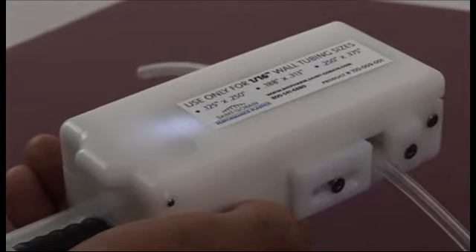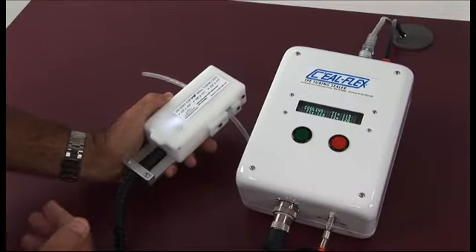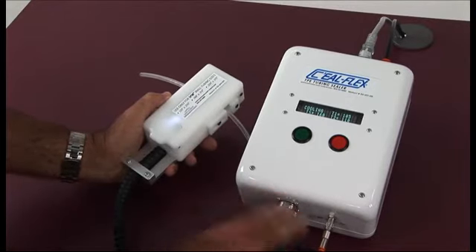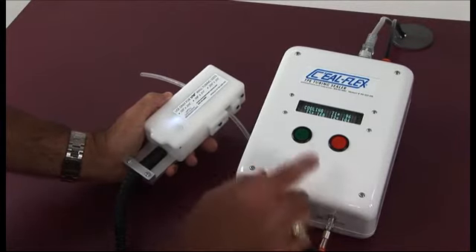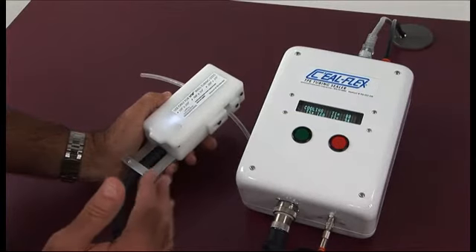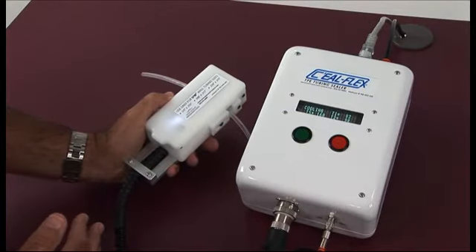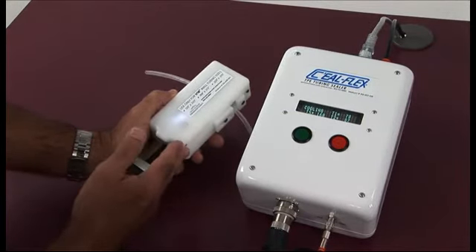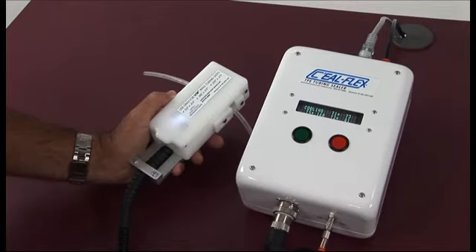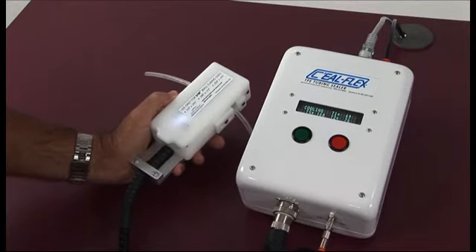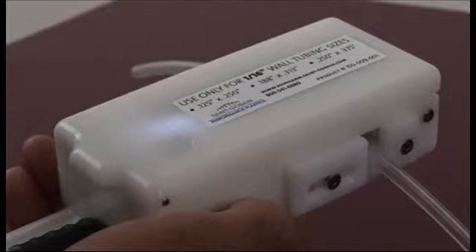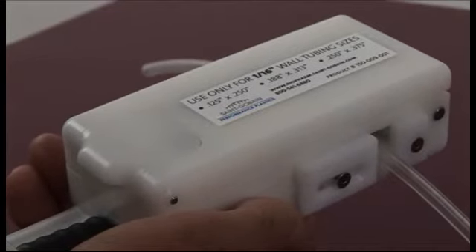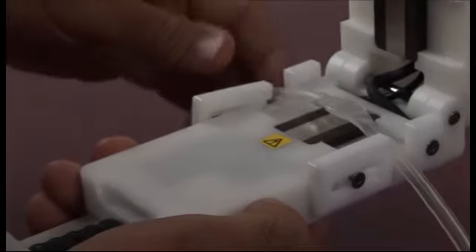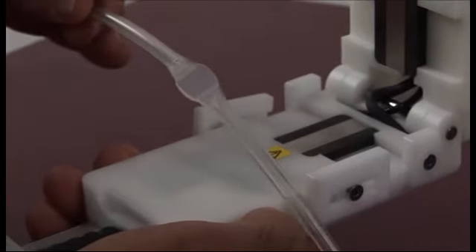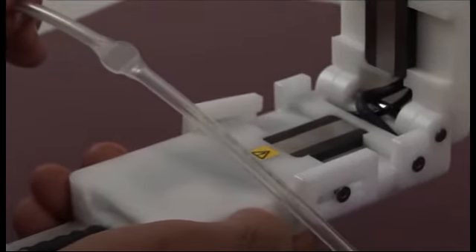This device can be operated without air, but the cool time will be longer. For example, instead of a 1-minute seal time on a 1/8 by 1/4 inch, you'll have approximately a 1 minute and 45 second seal. When the temperature reading on the head reaches 70 degrees or the optimum 33 seconds, you'll hear the device click. The light will go out. That means the head is unlocked and you can open it and inspect the seal. The device is now ready to make the next seal.